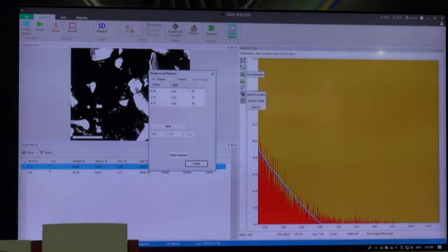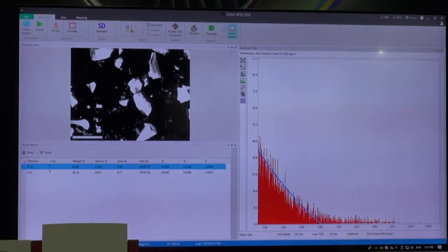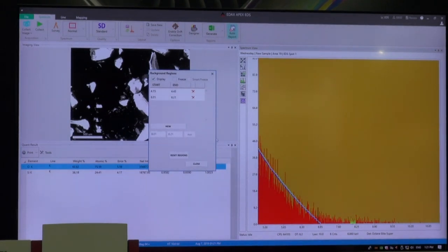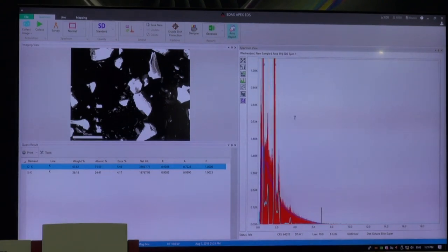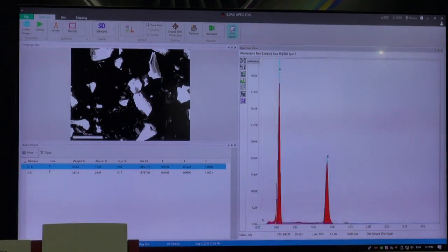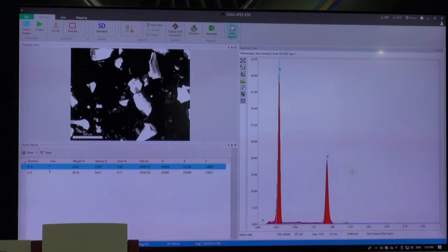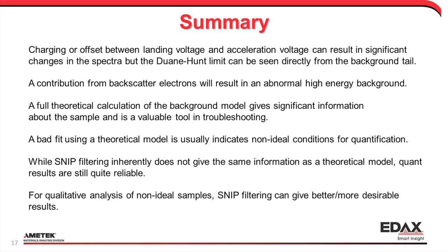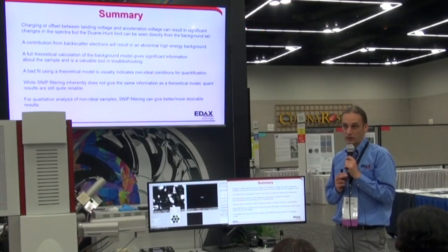Right now we have it anchored with one fit region. If I use a single high energy fit region and something is wrong, it tells us we have a misfit — don't click the quant button unless you figure out what's really going on. You can change the landing voltage and get a better result, but at the end of the day your sample is charging, and that's the main issue. If we have charging samples, you can see that in the tail — you can read the Duane-Hunt limit directly from the background tail and compare it to the landing voltage. That tells you if your samples are charging. Backscattered electrons hopefully you shouldn't see, but it depends on your detector.